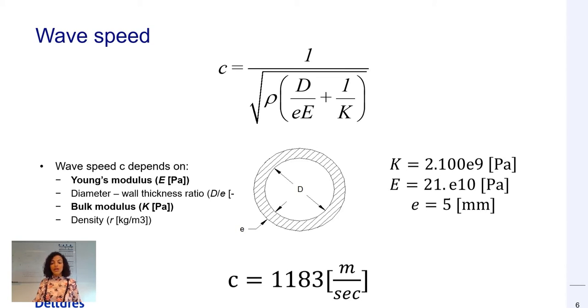Where c, the wave speed in the pipe depends on the liquid density, the pipe's diameter to wall thickness ratio, Young's modulus and bulk modulus. Young's modulus which stands for the pipe's elasticity depends on the pipe's material and the bulk modulus stands for the volumetric compressibility of the liquid.